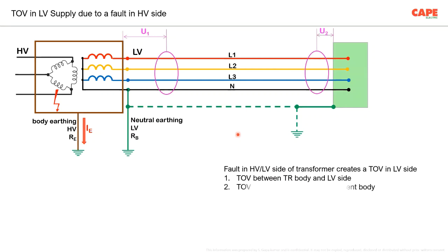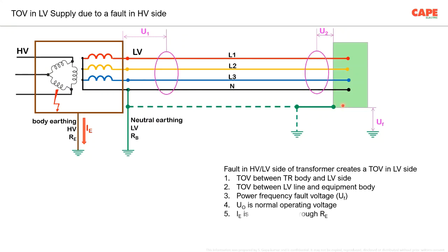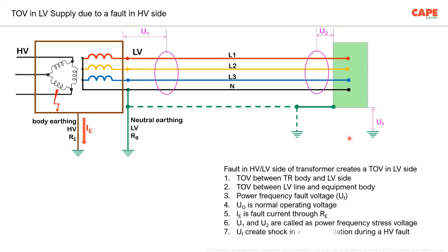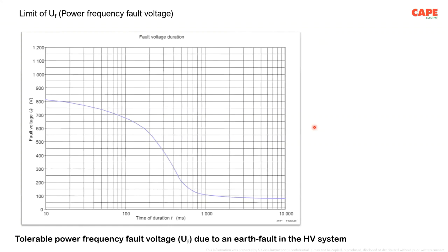It is going to create three issues. First is an over voltage, a stress on your transformer low voltage winding, a stress on your equipment, a stress or a shock voltage between the equipment and the local earth. These are the problems which are expected. U1, U2, UF. In the presentation, probably you will be seeing U1, U2, UF, but just to be sure: U1 means the stress at the transformer low voltage winding, U2 is the stress at the equipment, UF is the shock voltage.